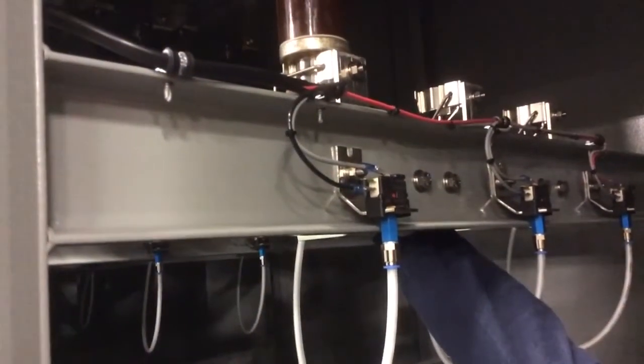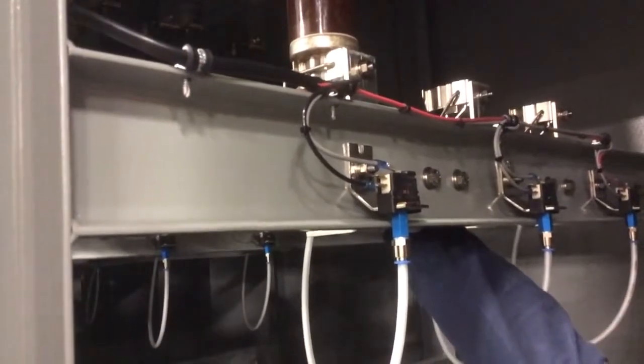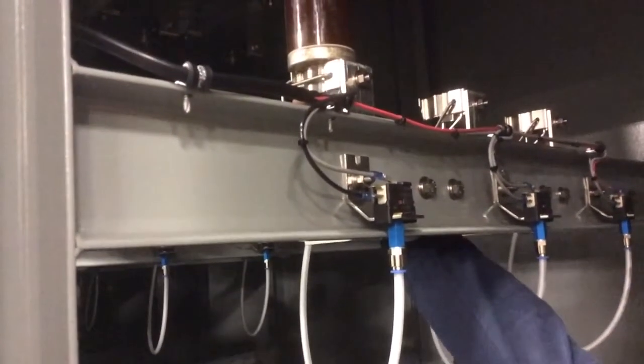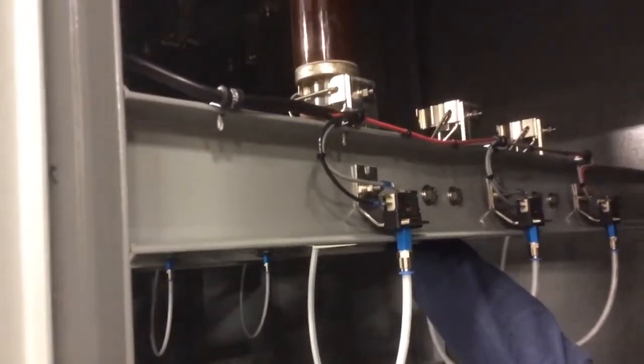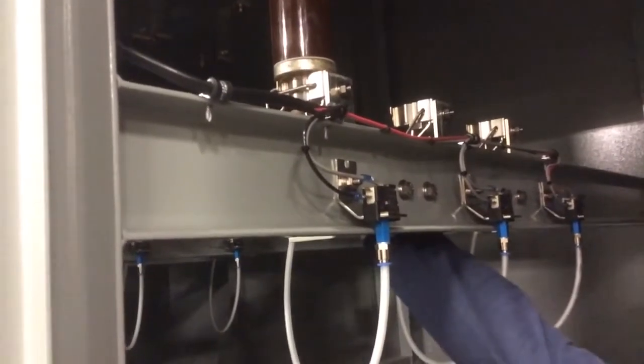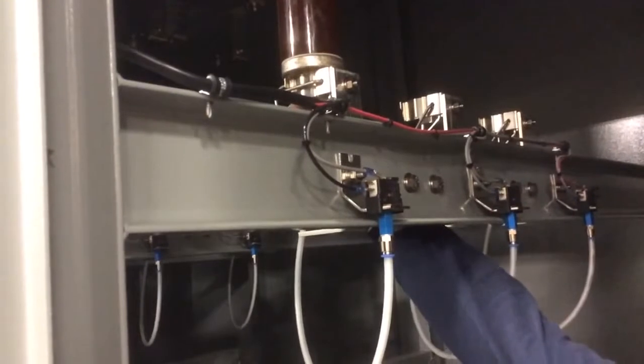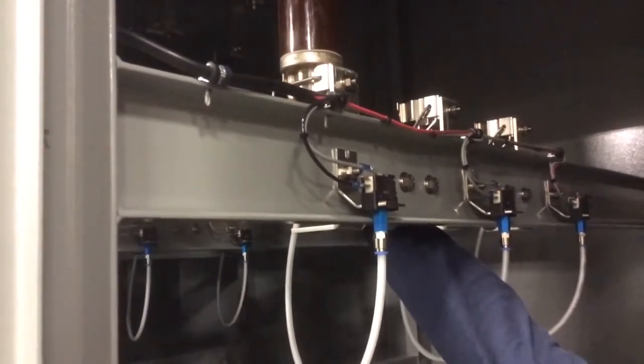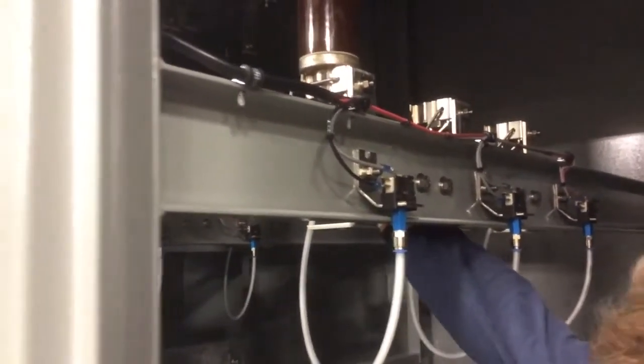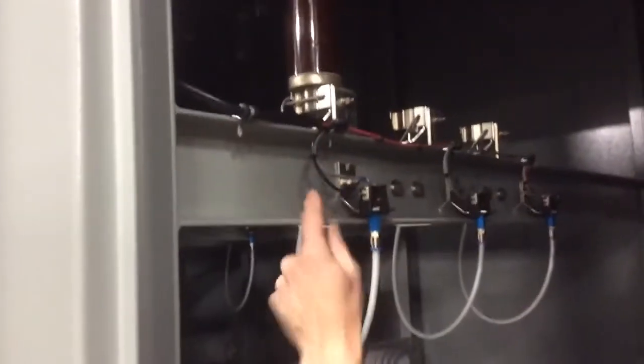A red flag appears in the window here, and you need to make sure that it's operating freely with no kinks in the line. When you operate this plunger, you can hear the switch transfer.